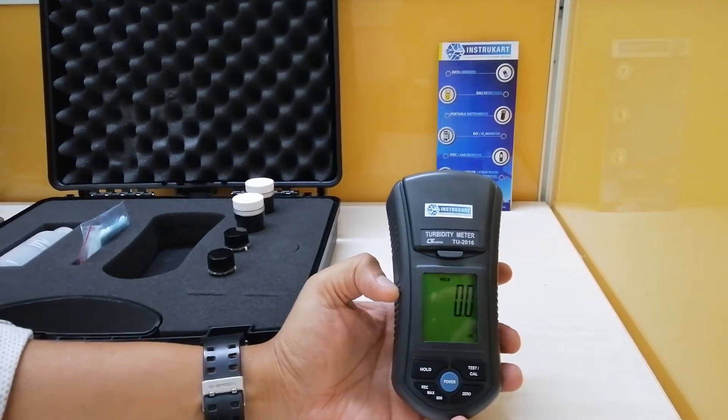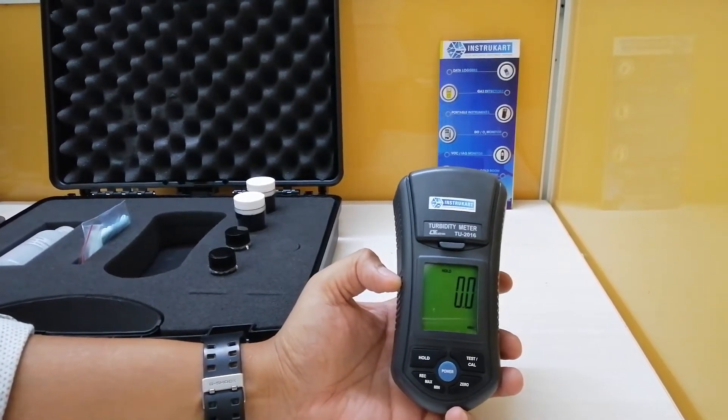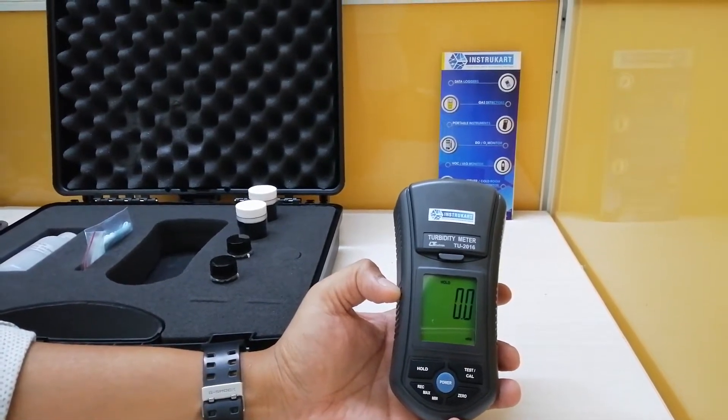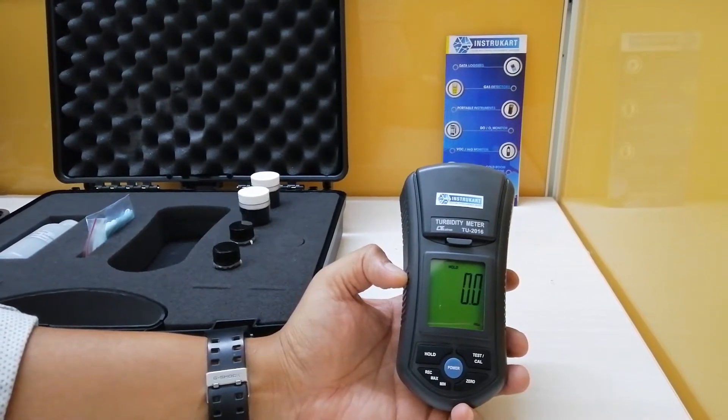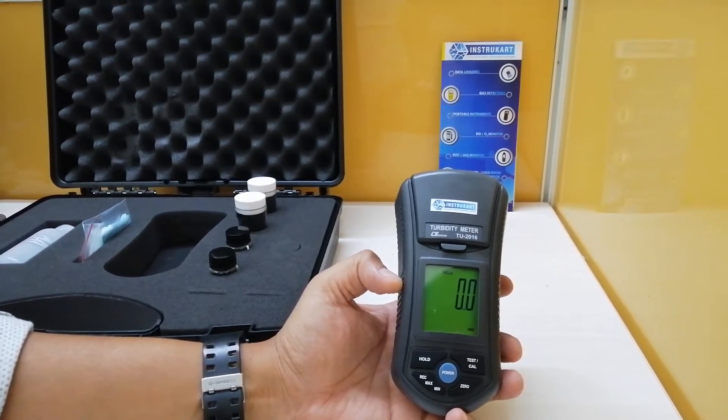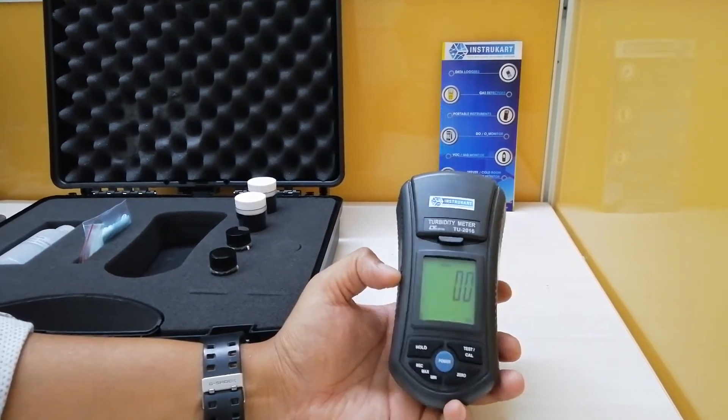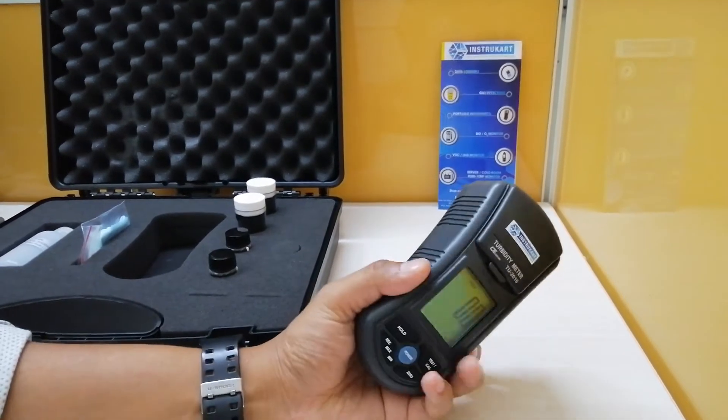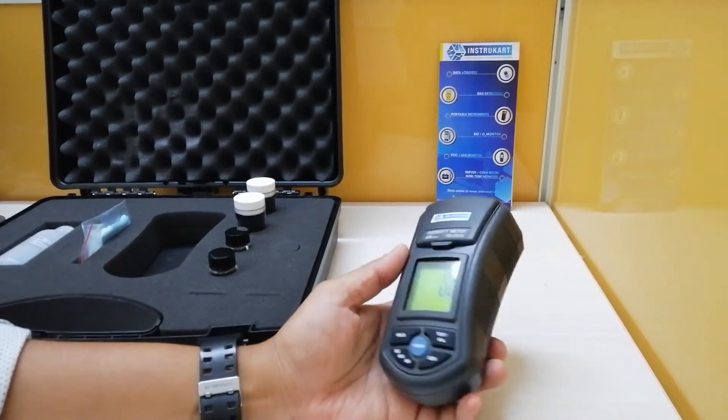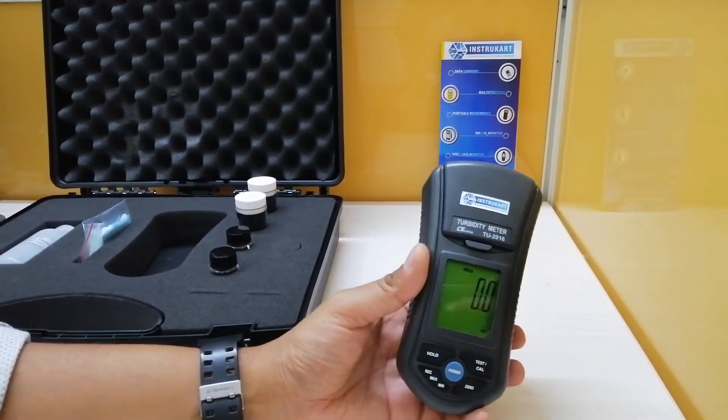For other specifications, it has an accuracy of 0.00 to 49.99 NTU with a resolution of 0.01 and plus or minus 5 percent reading, or 0.5 NTU plus or minus, whichever is greater.